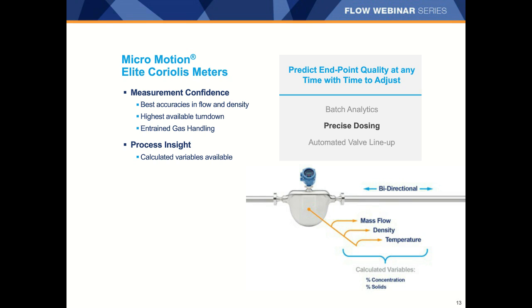And with good sizing, you can select a Coriolis meter that would accurately measure the mass of a variety of materials being charged, reducing the need for multiple feed lines and reducing the need for pressure and temperature readings used for compensation, and providing the most accurate measurement technology.